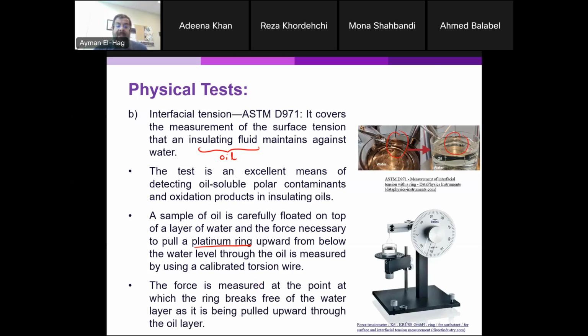water layer, okay? So now let's understand what this means, okay? When the oil and the water are closer to each other, meaning that we have more polar contaminants, because water is a polar material actually, okay? Then it becomes easier and easier to pull out this platinum ring with a much lesser force. So for this test, the higher the needed force, the better the oil, meaning that the chemical composition of the water and the oil is completely different, okay? And there is no contamination in the oil.